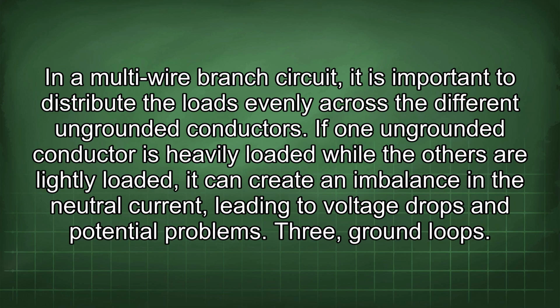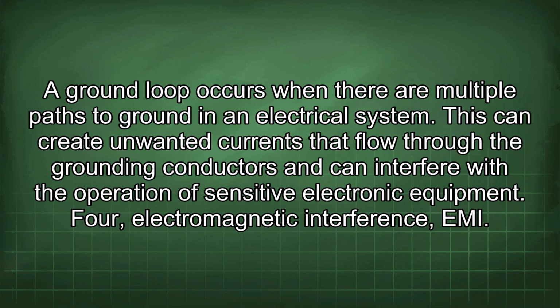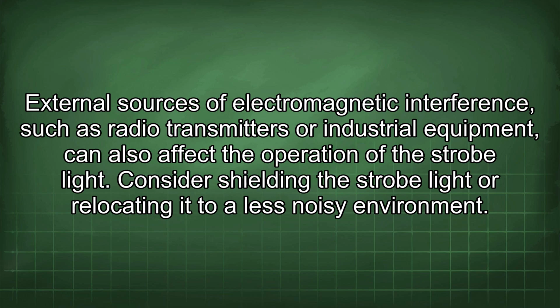3. Ground loops. A ground loop occurs when there are multiple paths to ground in an electrical system. This can create unwanted currents that flow through the grounding conductors and can interfere with the operation of sensitive electronic equipment. 4. Electromagnetic interference (EMI). External sources of electromagnetic interference, such as radio transmitters or industrial equipment, can also affect the operation of the strobe light. Consider shielding the strobe light or relocating it to a less noisy environment.